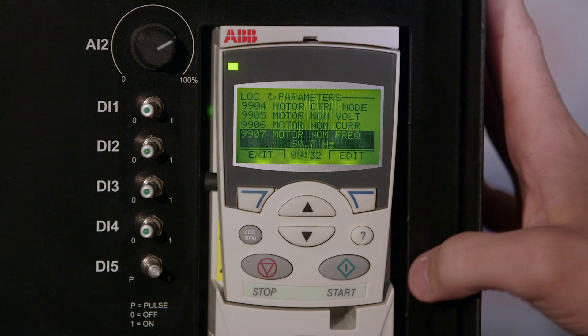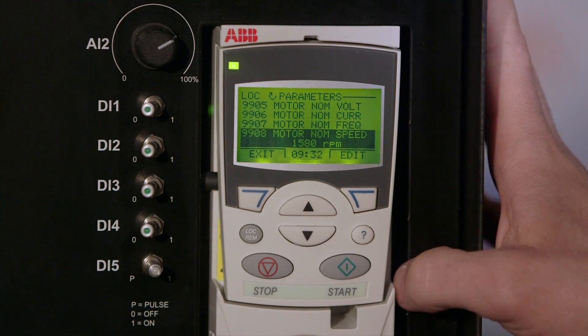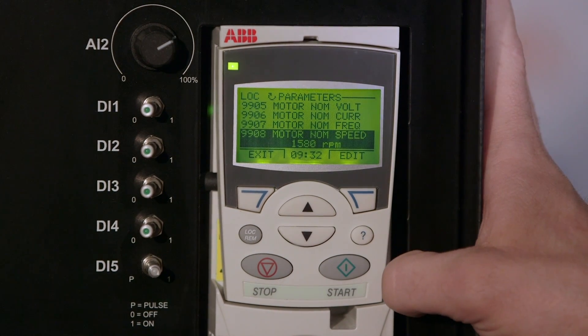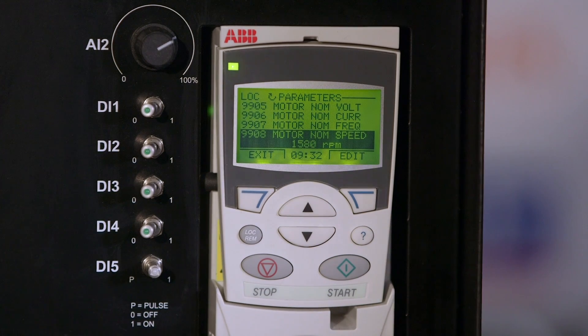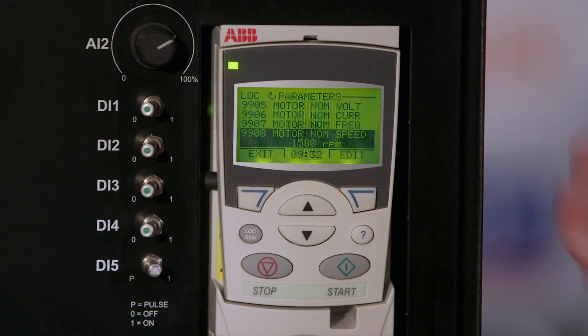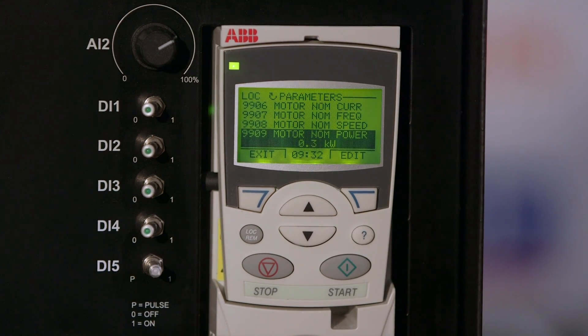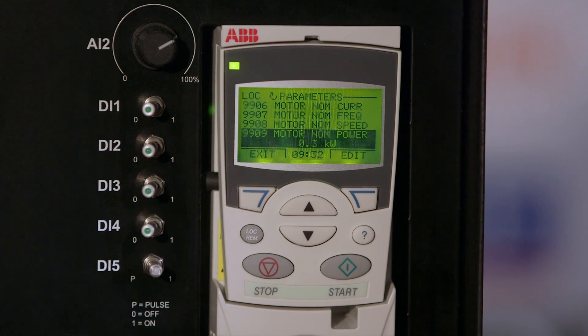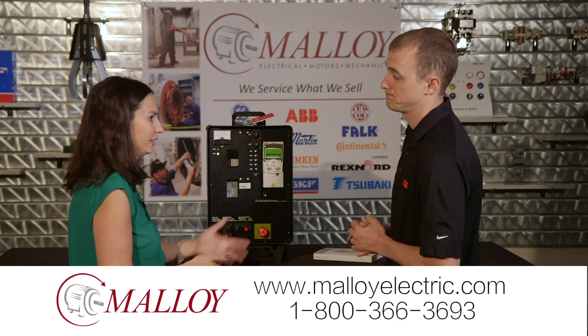Parameter 99.06 is the motor's current, and we have to input exactly what's on the nameplate — in this case 1.4 amps. Then frequency, 60 Hz. Parameter 99.08 is the nameplate speed of the motor: if it says 1745, put 1745 in. Finally, the power of the motor — in this case a 0.3 kW motor, so we put 0.3 kW in.